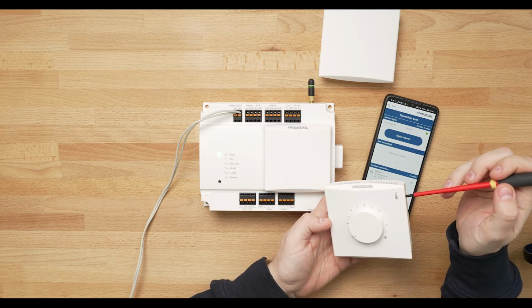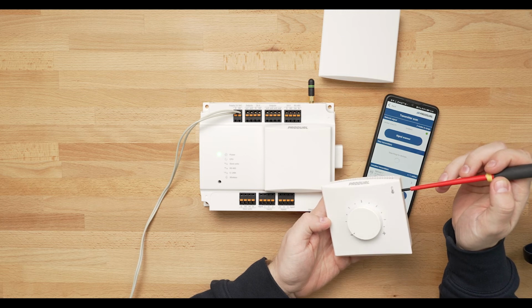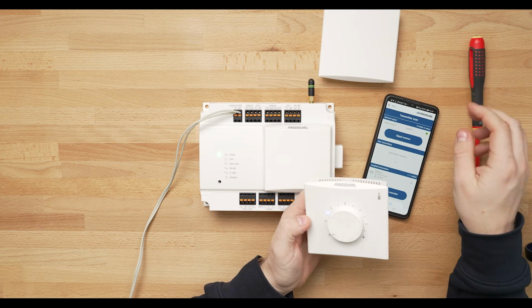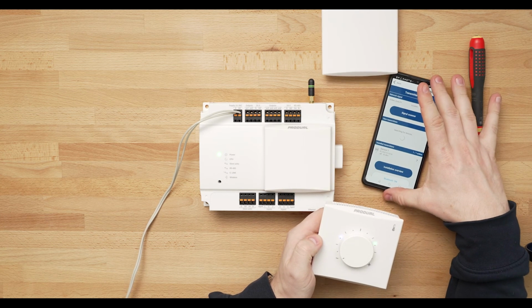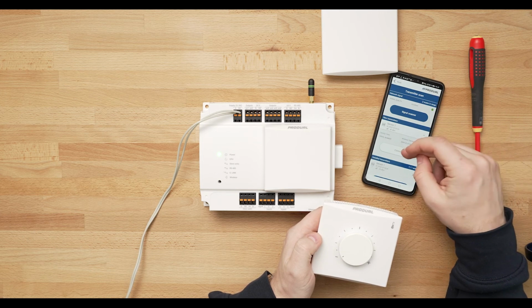In case we have a transmitter that is already installed to some other network or is just not in Bluetooth mode, we can activate the Bluetooth mode by pushing the button here on the side so that we will see two green LED blinks. Now it will indicate with the blue LED that the Bluetooth mode is on and we can have the connection with MyTool.